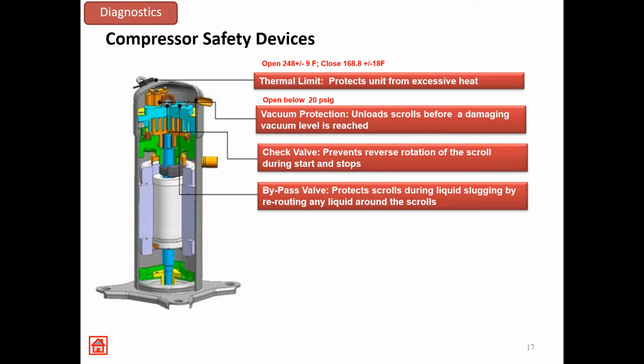All right, we're going to talk about our compressor. The Copeland compressor does have an internal relief. It will open around 280 degrees, but we cut it off prior to that. We intercept around 248. It says plus or minus 9 degrees, but I usually see around 250 to 251 on the job site visits I've been to. Then it's going to reset right around 170, 168, somewhere in that range. We do that, number 1, to keep the compressor from internally locking out. But number 2, when this top cap opens and there's heat on top of the compressor, we know it's getting hot, and it sends a signal to our control. That's one of our alarms that says the compressor is hot, and it lets you know that.